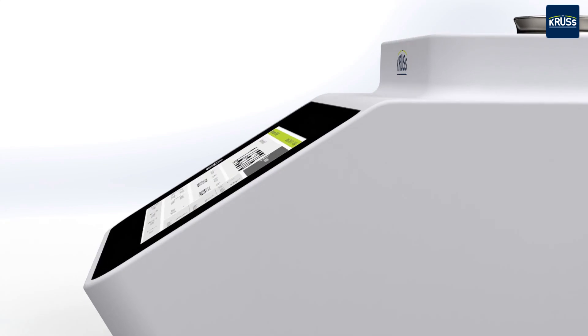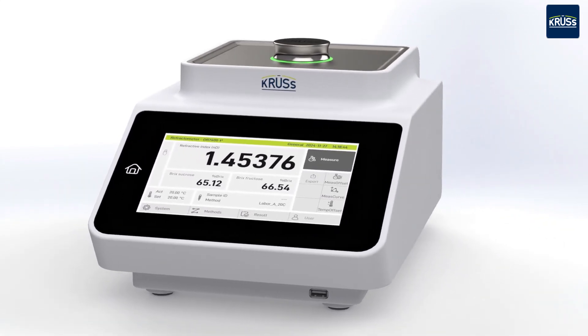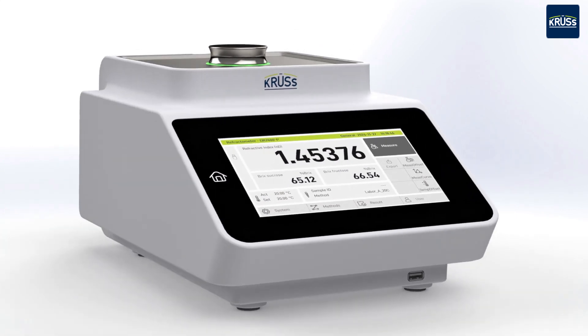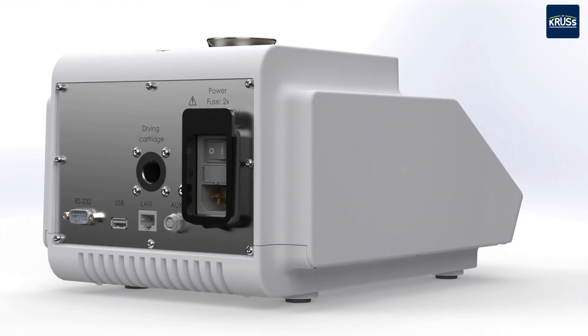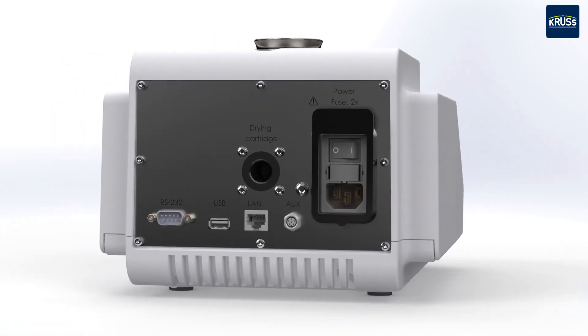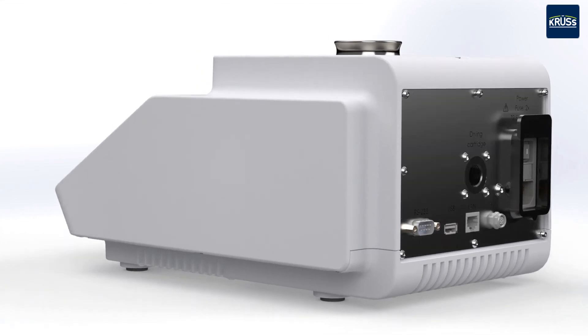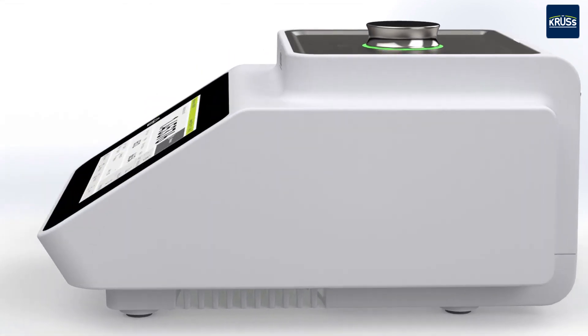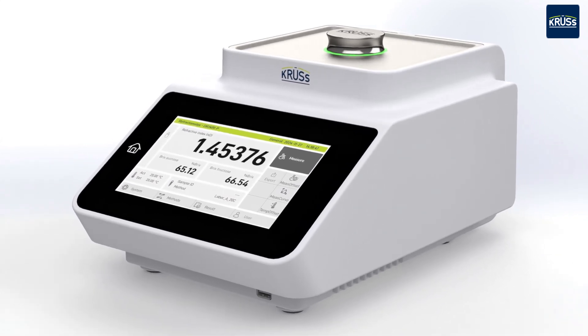With the modern KRÜSS laboratory refractometers of the DR7000 series, you can measure the refractive index and concentration of liquids and pastes with high accuracy in seconds. The DR7000 refractometers use precise internal Peltier temperature control to automatically temper samples to an accuracy of plus or minus 0.03 degrees Celsius.